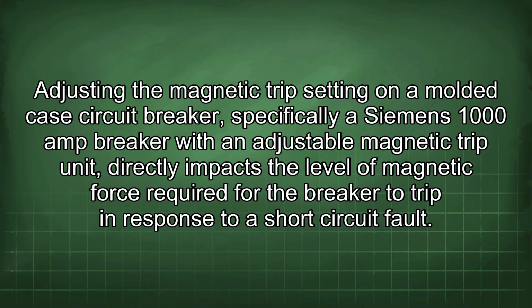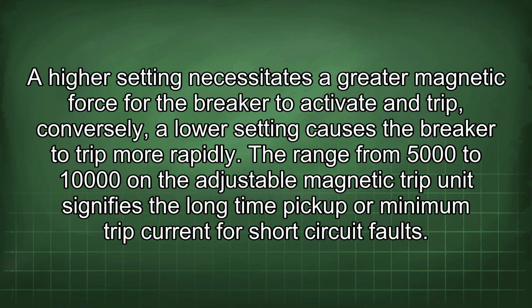Adjusting the magnetic trip setting on a molded case circuit breaker, specifically a Siemens 1000 amp breaker with an adjustable magnetic trip unit, directly impacts the level of magnetic force required for the breaker to trip in response to a short circuit fault. A higher setting necessitates a greater magnetic force for the breaker to activate and trip. Conversely, a lower setting causes the breaker to trip more rapidly.